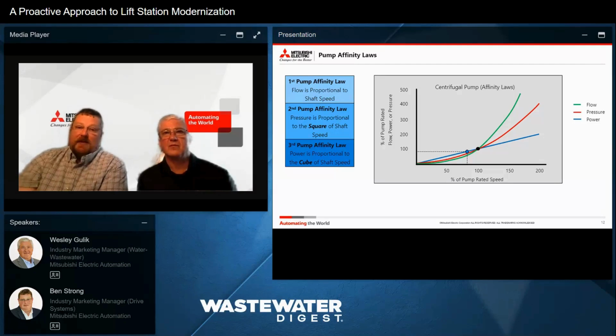Flow is proportional to the motor speed. Power is cubed. So we slow down a little bit, not below the minimum speed for your pump, because most of our pumps have minimum speeds, and we have the operational range that we've calculated for this pump where we want it to operate. But if we slow it down a little bit, we reap huge amounts of savings in power, some up north of 20% if we're running steady state. So that's something to keep in mind.